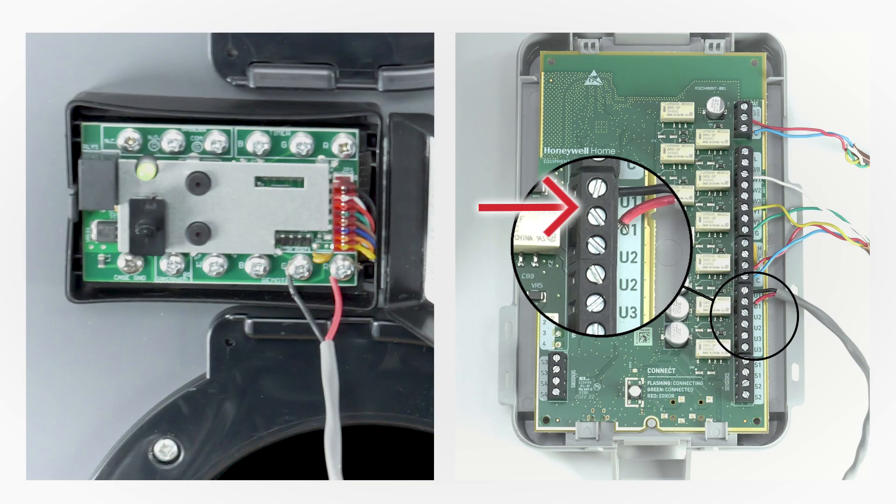You can also wire the T10 Plus to an equipment interface module or an EIM. An EIM makes it easy to control a ventilator from the thermostat when there aren't enough wires to the thermostat. If an EIM is used with the T10 Plus, then you can use the U1, U2, or U3 connections on the EIM.